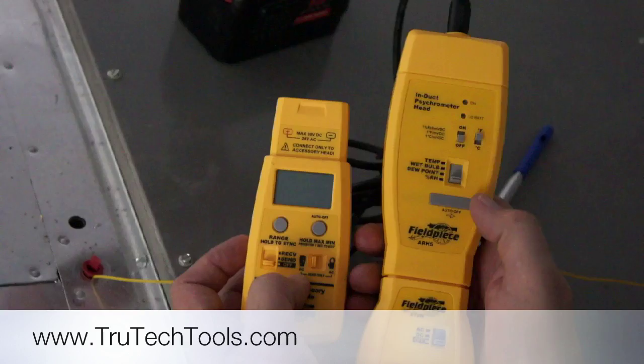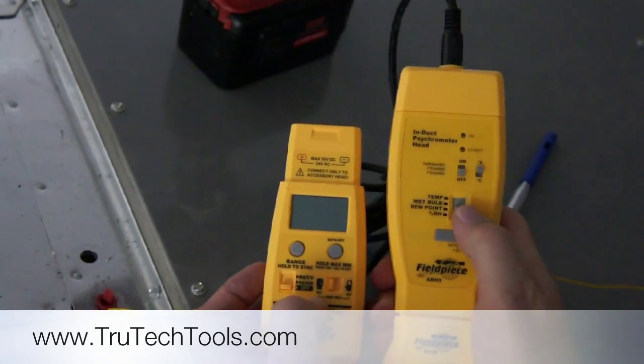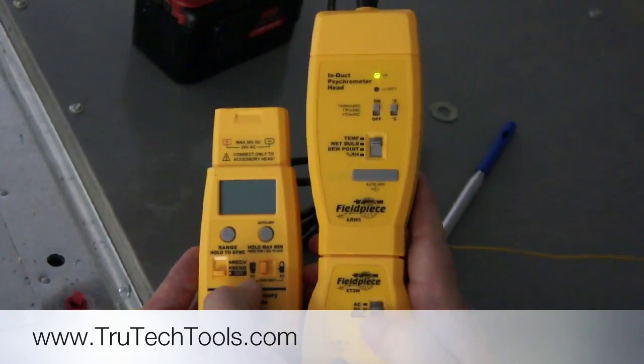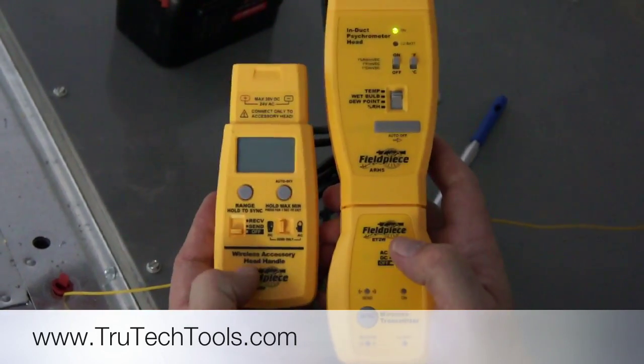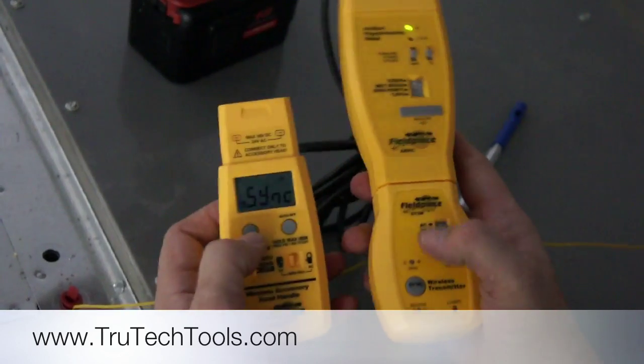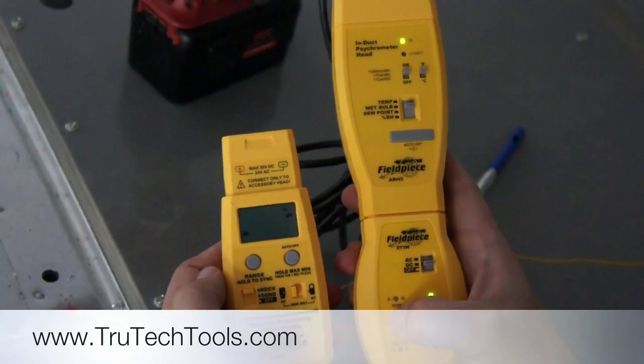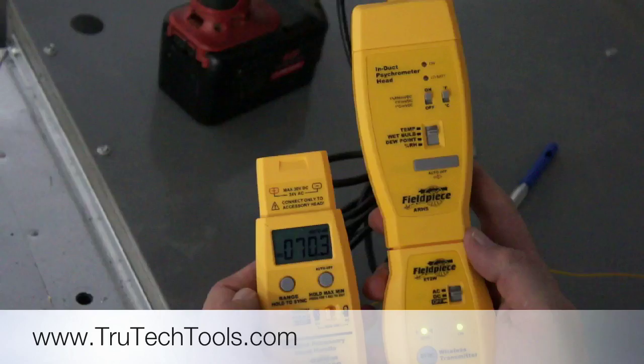Making all this work is really easy. I'm going to set my psychrometer to measure wet bulb temperature — I have that set to wet bulb. I'll turn my in-duct psychrometer head on, turn my ET2W to DC, and then turn my wireless accessory handle here to receive. The sync comes up — I press and hold the sync key here, hold it, and you'll see it start to flash. And now we've got wet bulb temperature.